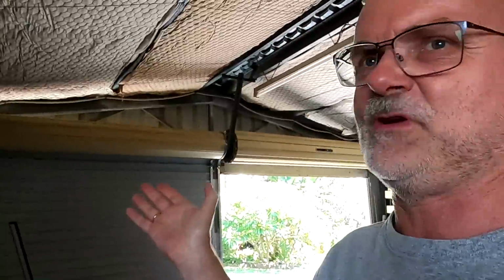As I said, the breaker here is rated 100 amps, but it's actually turned down to 80%, so it's on 80 amps at the moment. So I can't run this 105 amps for too long, but I'd guess around half an hour, 45 minutes would be fine before the breaker starts warming up and then triggers and turns off.